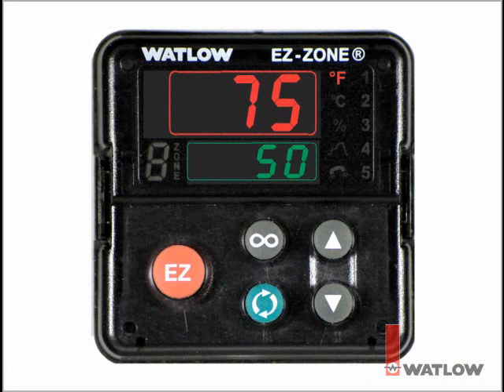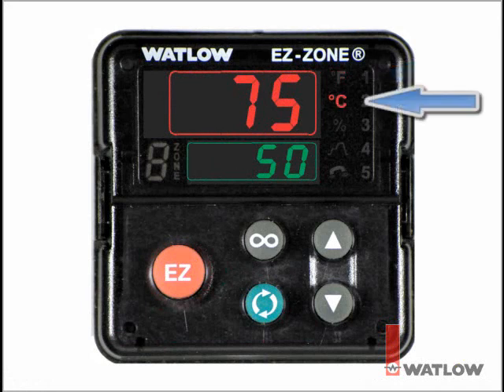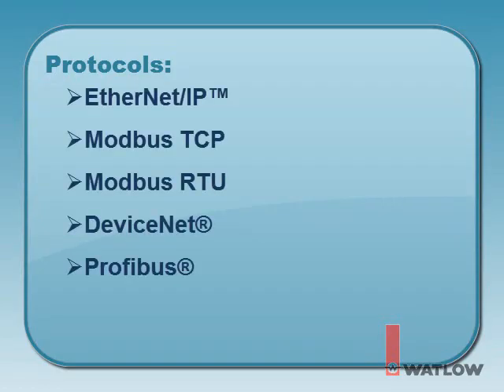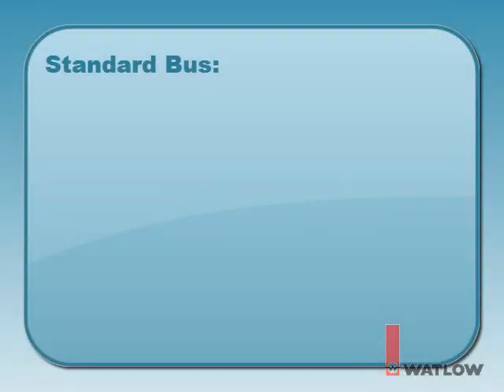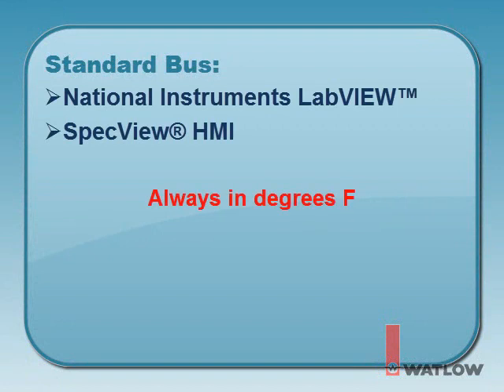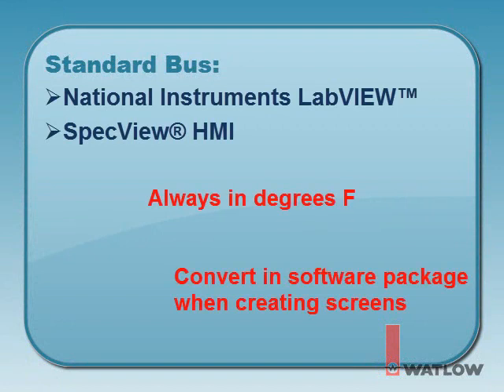EZ-ZONE models with a seven-segment display may be set to display temperature-related information in degrees Fahrenheit or Celsius. Models utilizing serial or Ethernet protocols may be set independently to transfer temperature-related information in degrees Fahrenheit or Celsius. Models using standard bus serial communications with National Instruments LabVIEW or SpecVIEW HMI software will always transfer temperature-related information in degrees Fahrenheit. These software packages have means within them to perform temperature conversion if required.